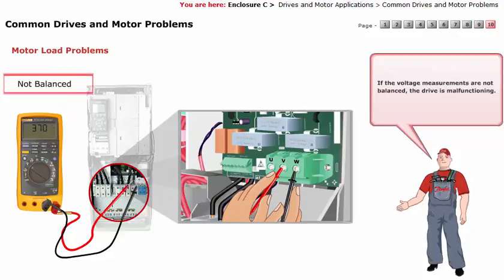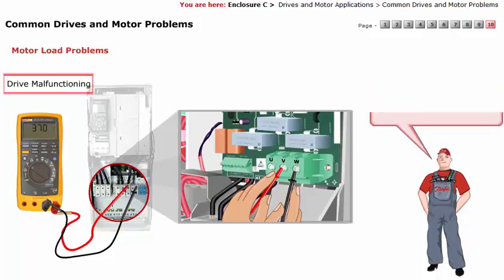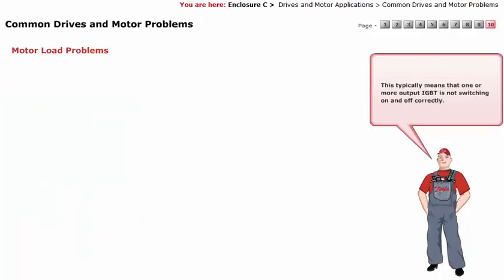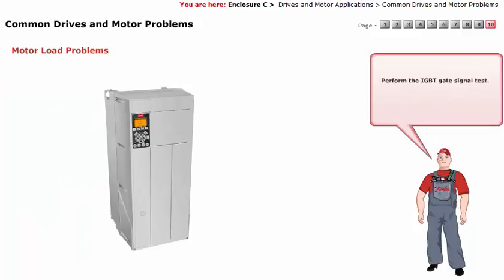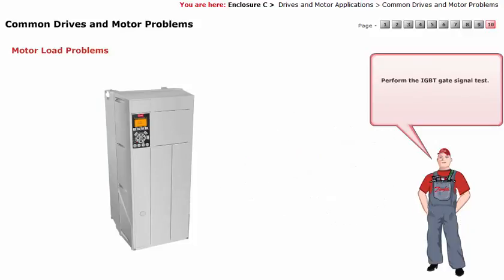If the voltage measurements are not balanced, the drive is malfunctioning. This typically means that one or more output IGBTs are not switching on and off correctly. Perform the IGBT gate signal test.